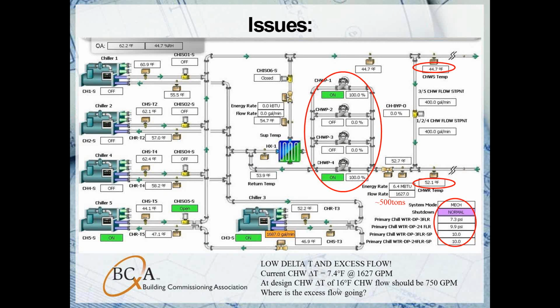At the bottom here, you'll see the design delta T is 16 degrees, and like I said, we're running between 7 and 8 delta T from supply to return, and our flow here is 1600. At these parameters, we're at about 500 tons on the plant. If we were at our design delta T, we would only be running 750 GPM, which is much less than 1 pump, because these pumps are sized at around 1600 GPM.